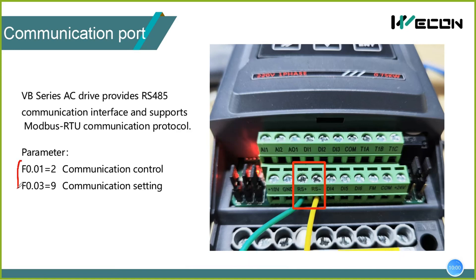Before using ModBus communication, you need to set the inverter parameters F0.01 and F0.03. These parameters control communication control and communication settings. Then connect HMI or PLC through the RS port on the terminal.